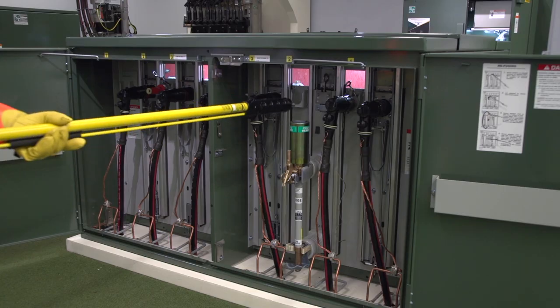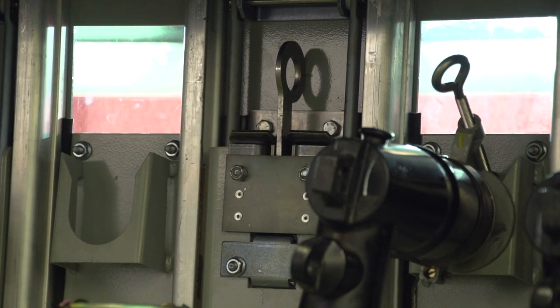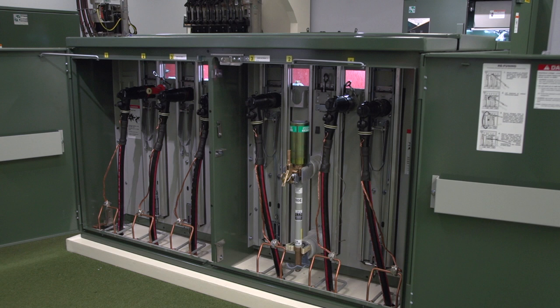Disengage the shotgun stick from the pull ring. Using the shotgun stick, push against the top of the mounting to verify that it has securely latched. With the fuse mounting latched in the open position, the fuse is de-energized, isolated from high voltage, and accessible for removal from the mounting. Do not close a door on a fuse mounting in the open position with a fuse in the mounting, as the door will strike the fuse pull ring and interfere with door closing. The door may be closed if the fuse is removed from the mounting.